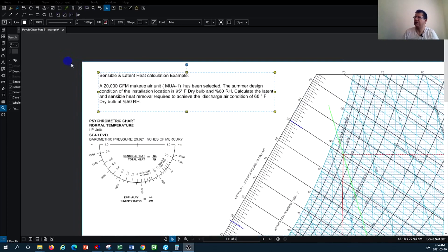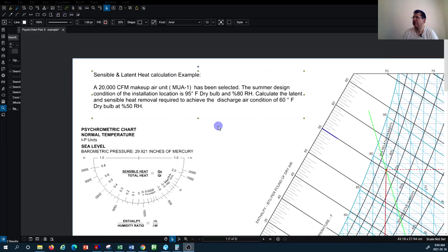If you remember from the previous tutorial, we had a condition with a makeup air unit of 20,000 CFM. The outdoor design condition was 95 degrees Fahrenheit with relative humidity of 80 percent, and we want to calculate the latent and sensible heat removal required to achieve the discharge air condition of 60 degree dry bulb and 50 percent relative humidity.